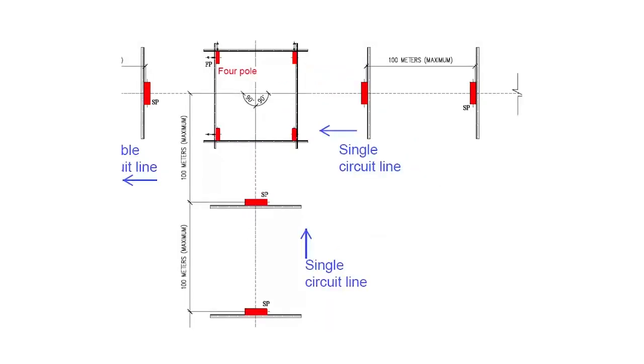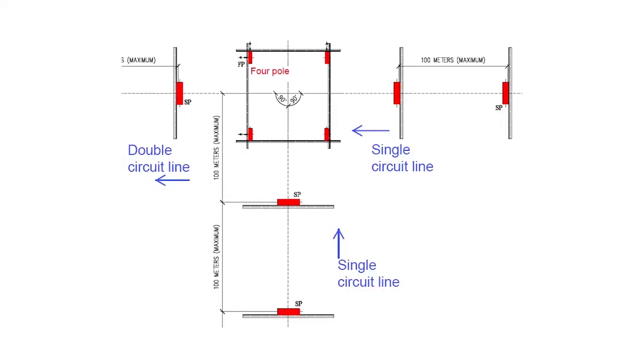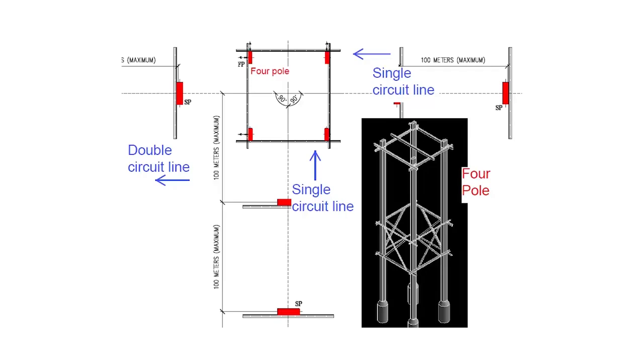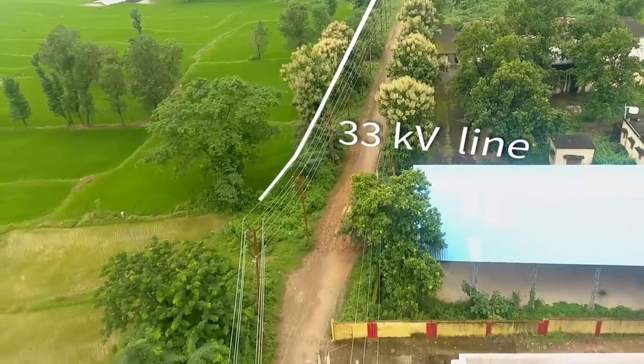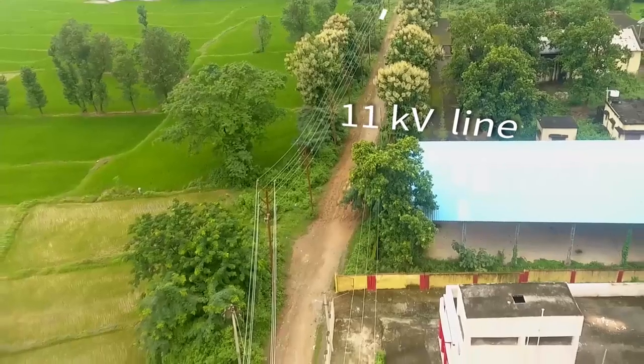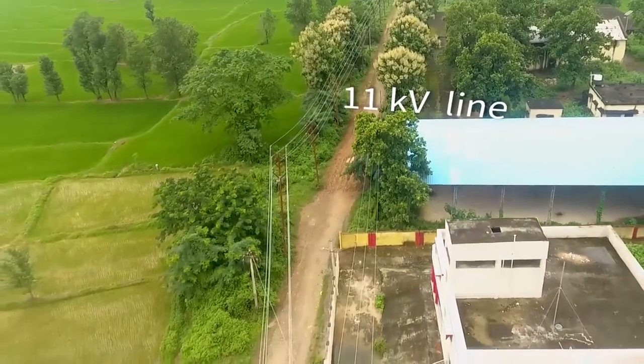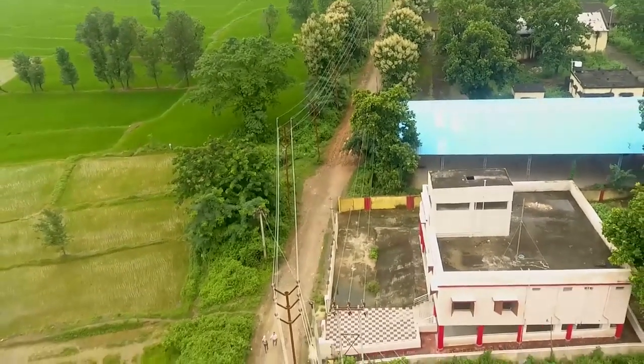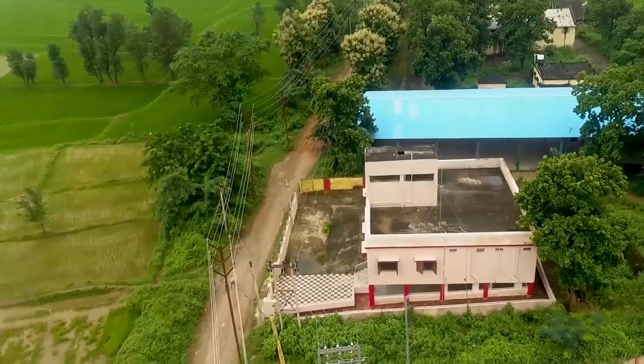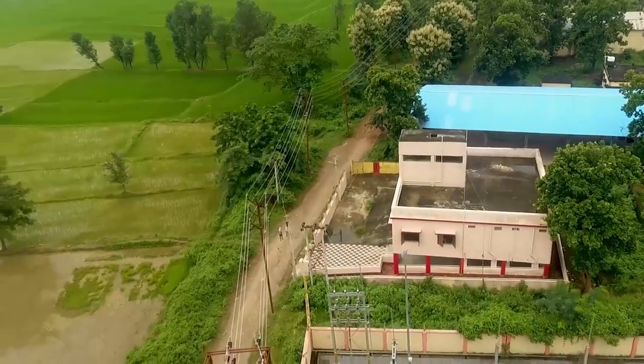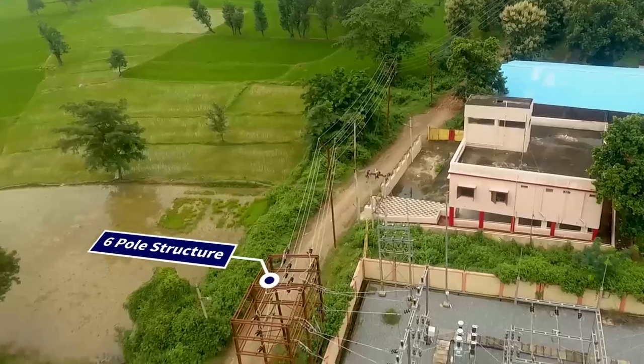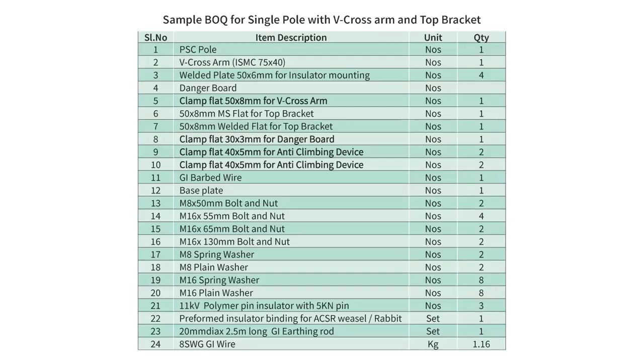Now let us see how a 4 pole structure is being used for taking tappings in either direction. A single circuit line is drawn, it reaches the 4 pole structure and it takes 2 directional lines, one on the left and one on the right. Thus the 4 pole structure is being used for taking both the tappings. Now, it is a 33 kV line which I have shown. The 11 kV line also will be done in the same fashion, a double circuit line, but the only thing is that the pole height and the insulator used for that is changed. Now it comes and gets into a 6 pole structure, after which it takes deviations. We will see how the BOQ helps you.